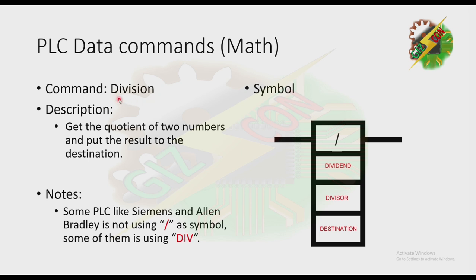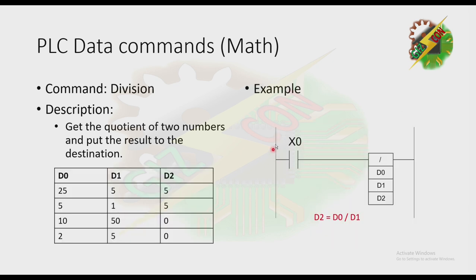Next we have Division — it gets the quotient of two numbers and puts the result to the destination. This is the symbol for this command. If X0 is energized, D0 will be divided by D1 and the result will move to D2. Take note: like subtraction, you cannot interchange D0 and D1, because you will get different values, unlike in addition and multiplication.